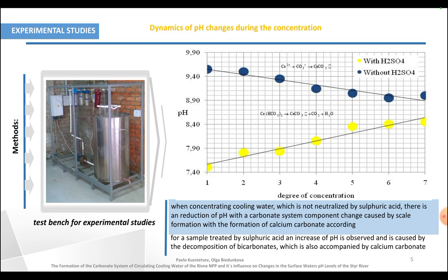Experimental studies were carried out using a test bench with operating conditions of CCS modeled, in particular evaporation and concentration and air aeration. The dynamics of pH changes during the concentration and aeration of cooling water samples with and without treatment by sulfuric acid are shown in the diagram.